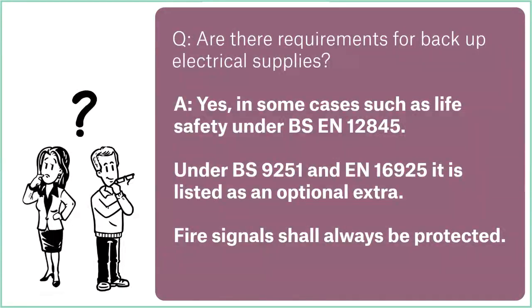Backups for electrical pumps are only required if you've got 2 electric pumps. So generally speaking, electrical backups for fire pumps are not required. If you've got 1 electric pump, then that's fine, if that is deemed suitable, a single supply, obviously. So yeah, one tank, 1 pump. You've got a single supply. That's deemed fine. If you're under life safety, then you would need a backup pump, but you could, of course, have a diesel pump. So again, the idea is that 1 electrical failure is not going to completely render the sprinkler system inoperable. So if the mains electricity goes down, you've still got your signals, and the electrical pump won't run, but the diesel pump will, and come to the rescue.